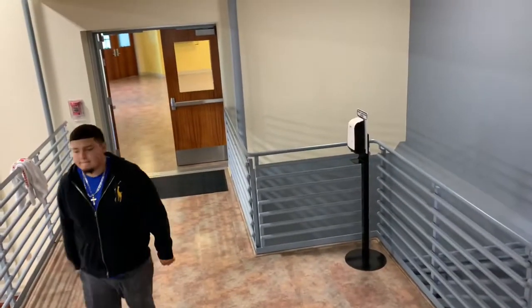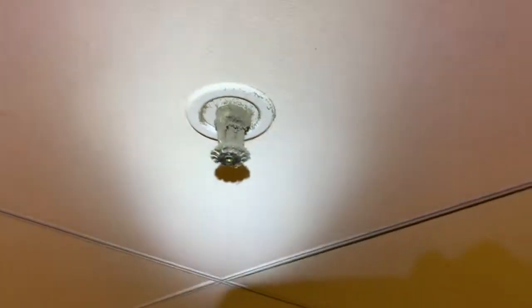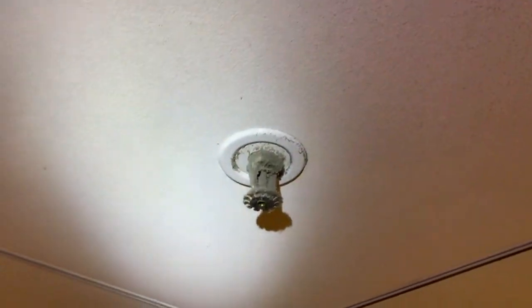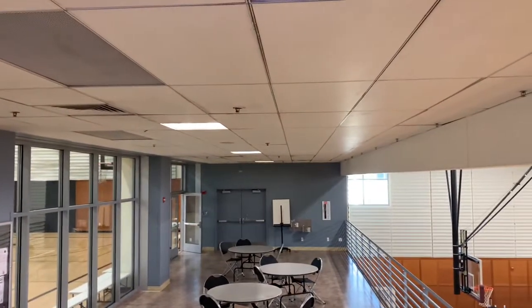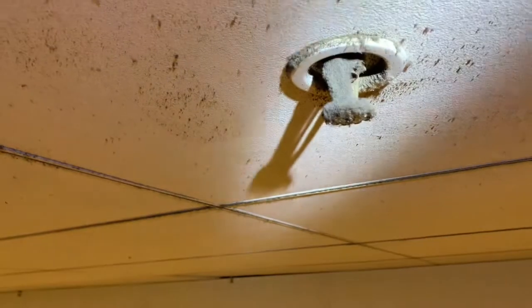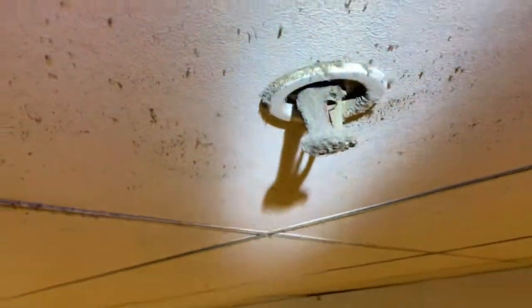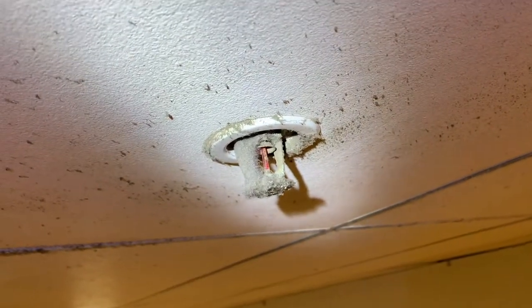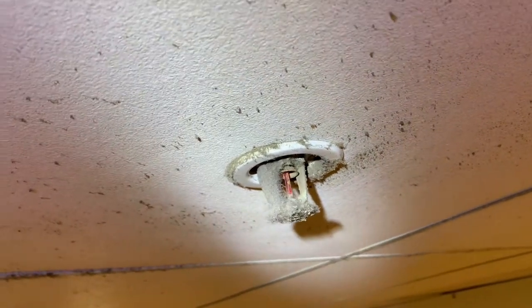It is apparent that we've got some loaded fire sprinkler heads here. If you ever want to see what a loaded fire sprinkler head looks like, there you go. We got about one, two, three, four, five — all these are loaded. This head is really loaded; it's probably got about a half inch worth of dust on it. There's no way I can really pass these now.